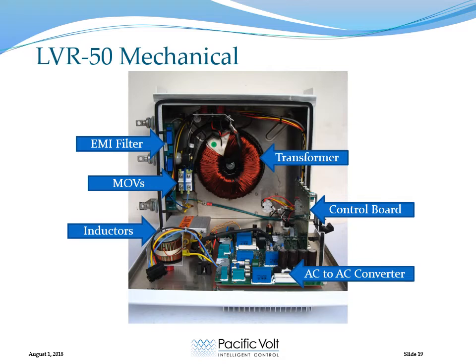This is what it looks like inside. This is the converter board that we talked about. Standing up here perpendicularly is the control board, which tells the converter board what to do. This is the series injection transformer. These are MOVs provided for transient protection. These are the EMI filters, and these two devices are input and output inductors. All of this is provided in a very compact and lightweight enclosure, especially considering it has a 50 kVA rating.